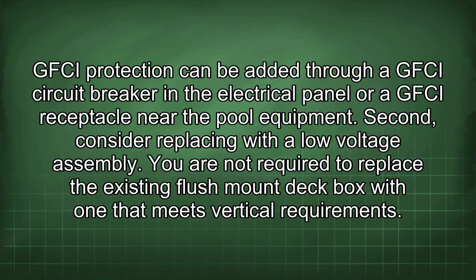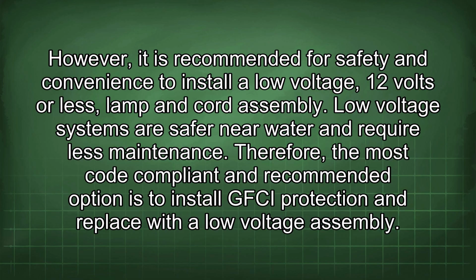GFCI protection can be added through a GFCI circuit breaker in the electrical panel or a GFCI receptacle near the pool equipment. Second, consider replacing with a low voltage assembly. You are not required to replace the existing flush mount deck box with one that meets vertical requirements. However, it is recommended for safety and convenience to install a low voltage 12 volts or less lamp and cord assembly. Low voltage systems are safer near water and require less maintenance. Therefore, the Code compliant and recommended option is to install GFCI protection and replace with a low voltage assembly.